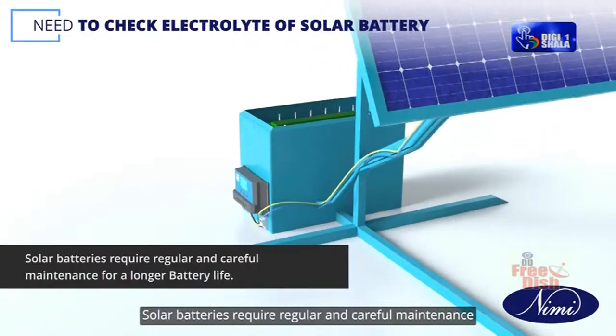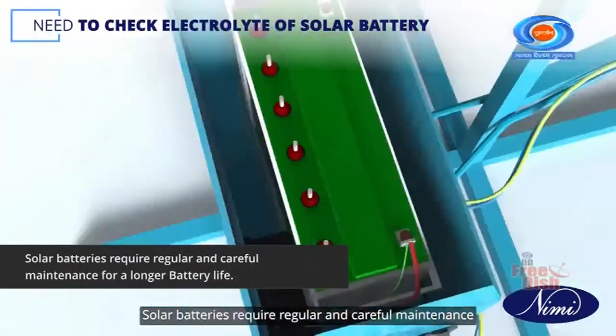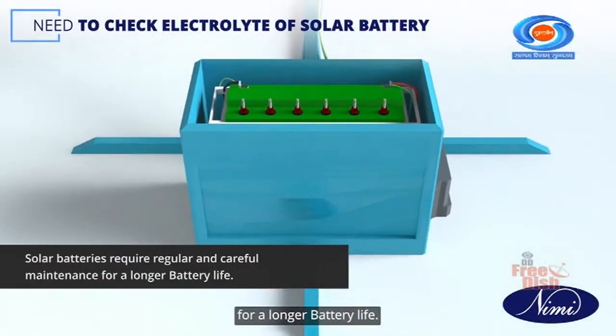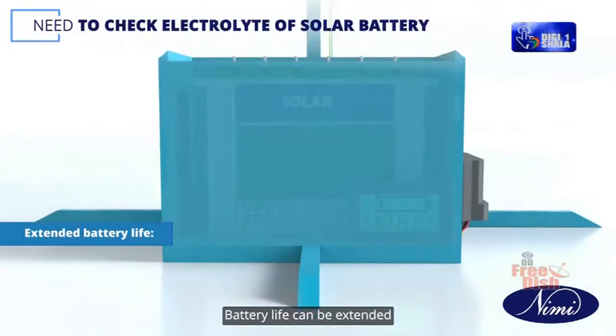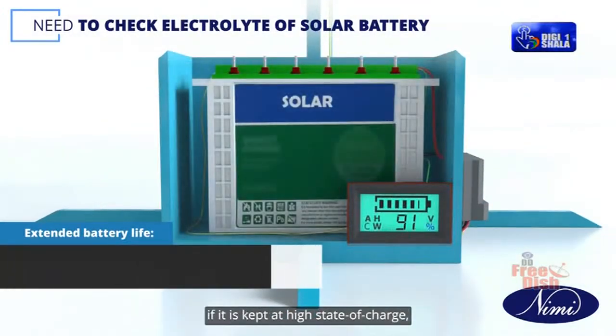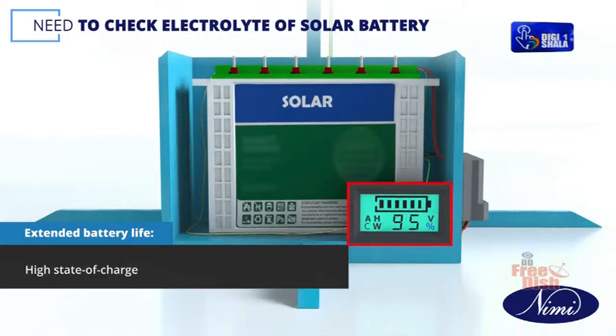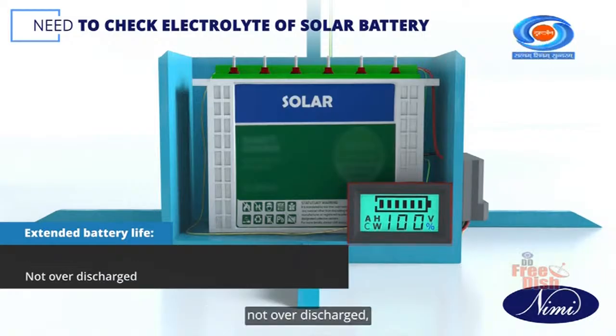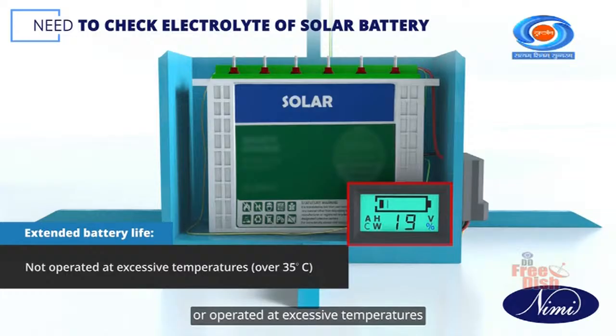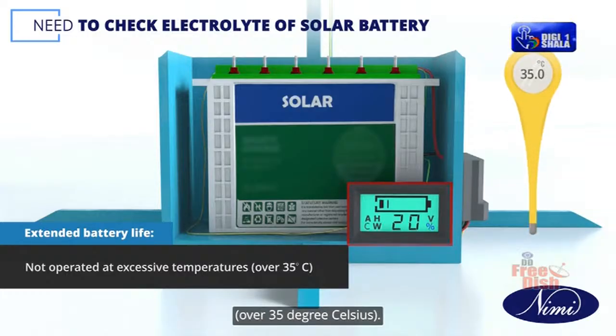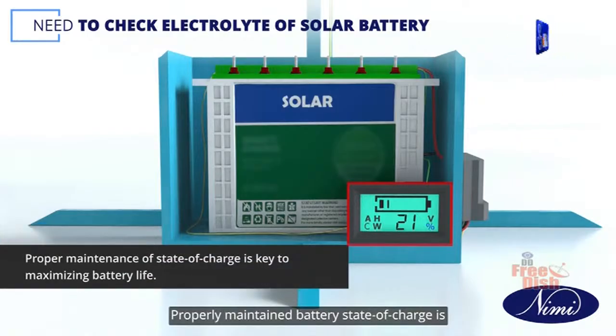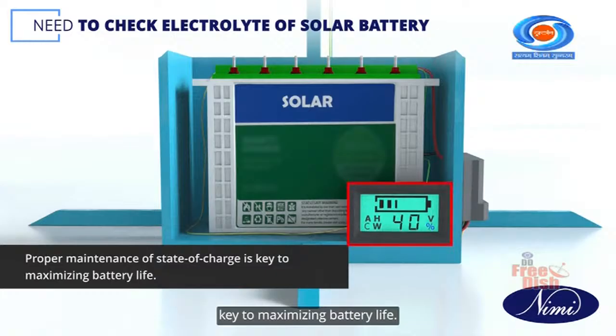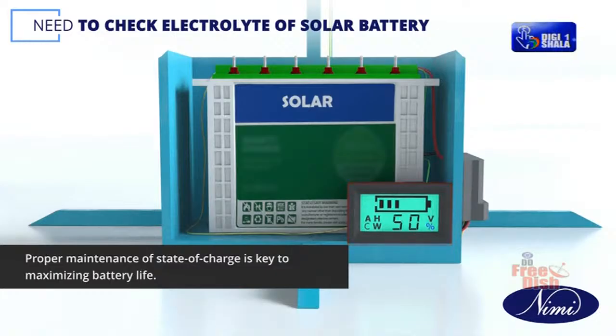Solar batteries require regular and careful maintenance for a longer battery life. Battery life can be extended if it is kept at a high state of charge, not over-discharged, or not operated at excessive temperatures over 35 degrees Celsius. Properly maintained battery state of charge is key to maximizing battery life.